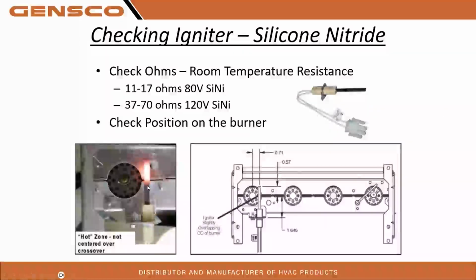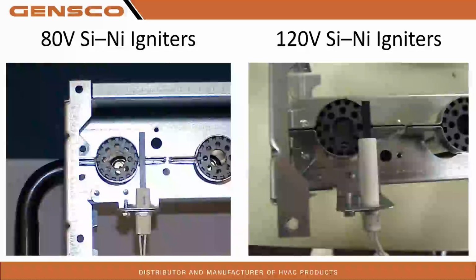Like you can see in this picture, this is an 80 volt and it is not over the hot spot of the igniter. So it is essentially too tall, right? This thing will light, but it'll probably light on the second attempt, which could create a heavy lighting situation and of course a concerned homeowner if they can hear that. So let's look at burner faces with proper placements. With proper placement in the hot spot, you're going to see the 80 volt igniter just at the edge of the venturi, right at the end of the diffuser. The 120 volt is coming over that cone just a little bit, just covering it, and that is right dead in its hot spot. So best reliability in the factory positions.